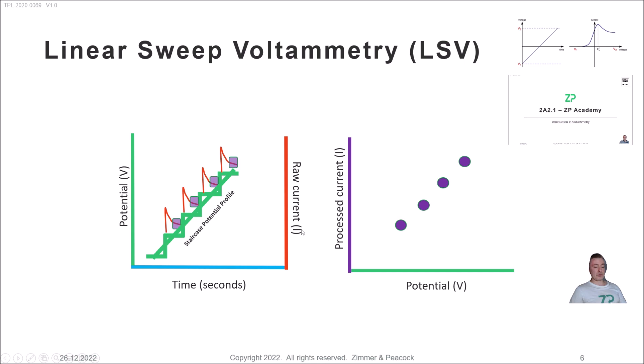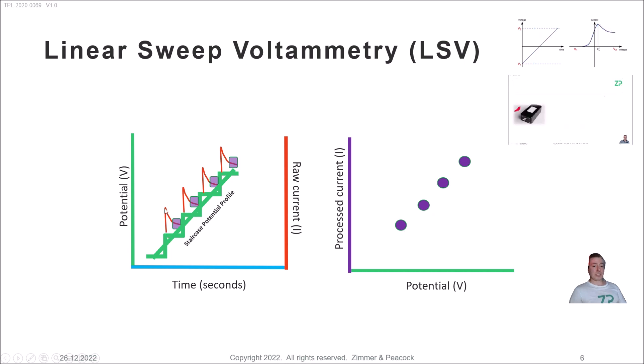Touching on linear sweep voltammetry: modern potentiostats are digital, not analog, so they apply a sweeping voltage in a stepwise staircase manner. Every time you change voltage you get a charging current, so you don't record the current at the beginning of the step. Instead, you wait until approximately the last 25% of the time period and then record the current. The current jumps up, starts to relax, then they record — this is what most potentiostats are doing, even if you don't necessarily know it.